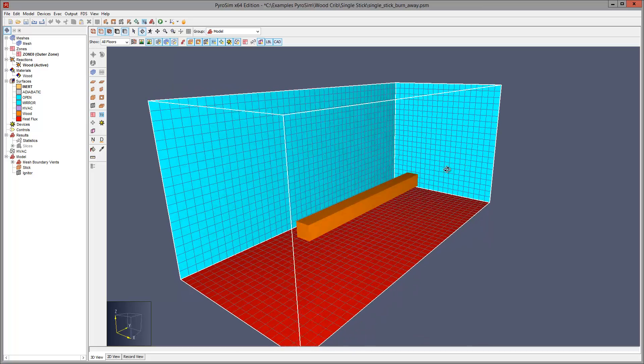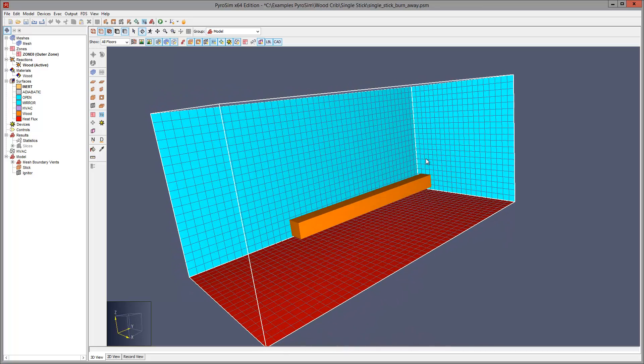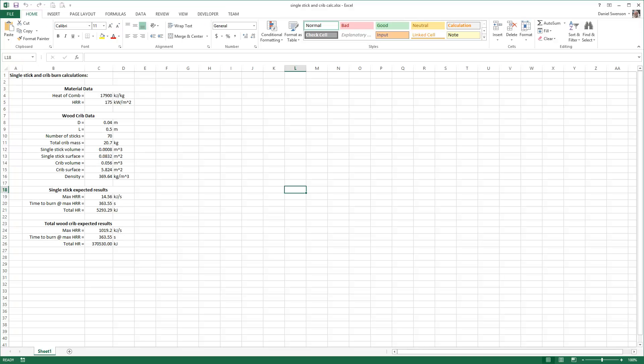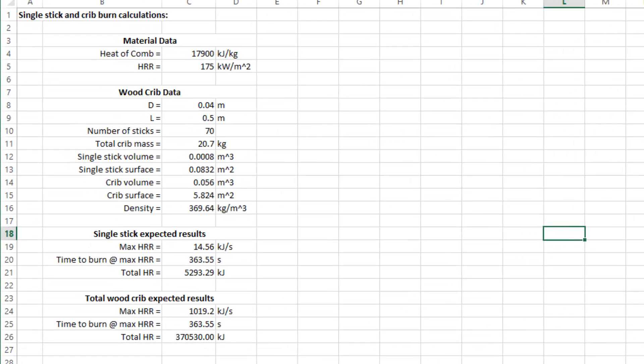Before modeling our wood crib in detail, let us burn a single stick using the same material properties and mesh size that we plan to use for our full analysis. The single stick is 40 millimeters on each side and 500 millimeters long. The mesh size is 20 millimeters. The heat release rate per unit area is 175 kilowatts per meter squared.